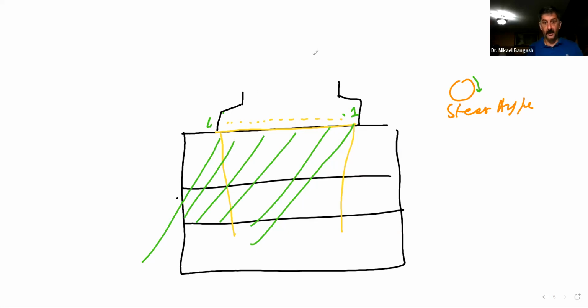We can turn it one more tick. It may go back to this, but then we give it one more click. And now all of a sudden the beam may be steered in this direction here. That mainly says now this will be the first PZT to fire, and this one here will be the last one to fire.